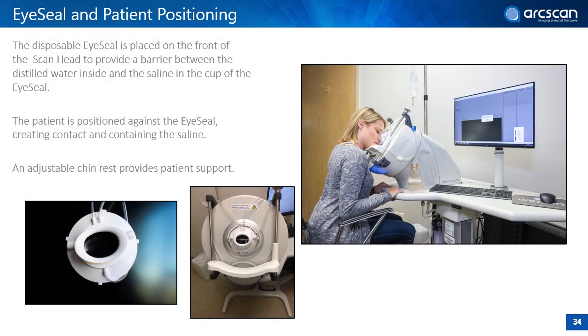How do we do that? Well, there is a disposable product called the eye seal, one per patient, that is attached to the front of the scan head. After the patient is positioned against the eye seal, the saline is released into the eye seal cup. So starting from the inside out, first you have distilled water within the scan head, the eye seal on the scan head, then saline in the eye seal cup, and the patient positioned against the eye seal.